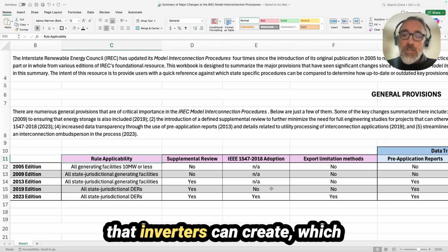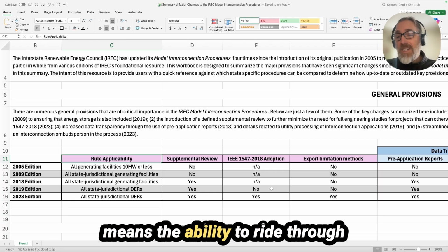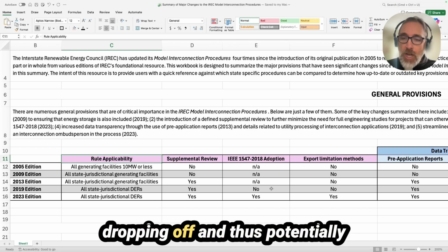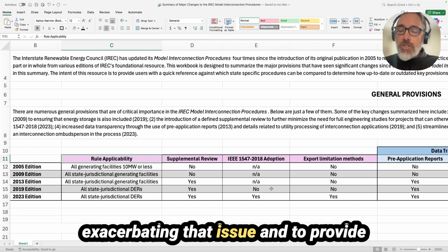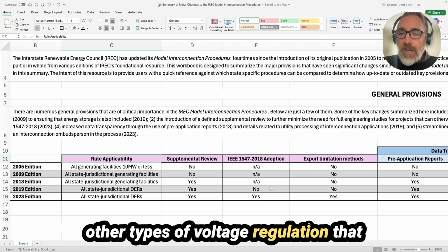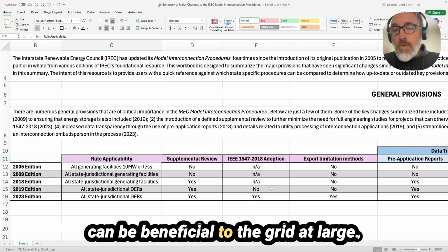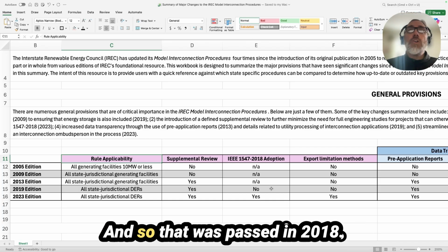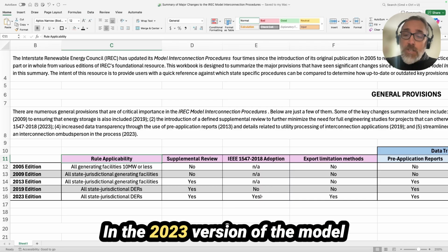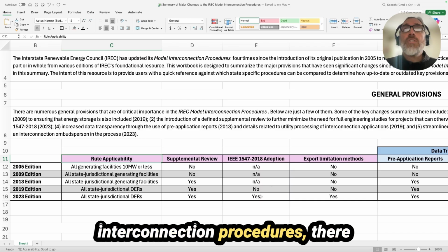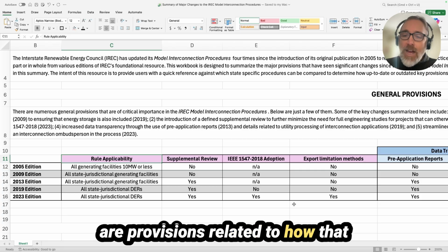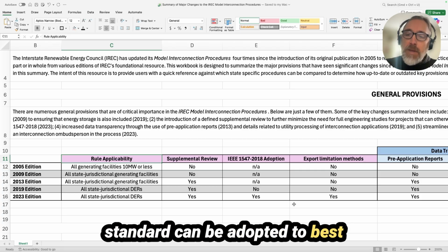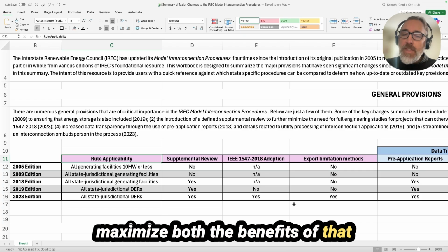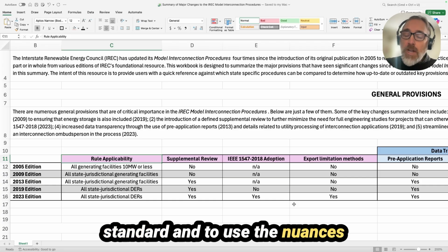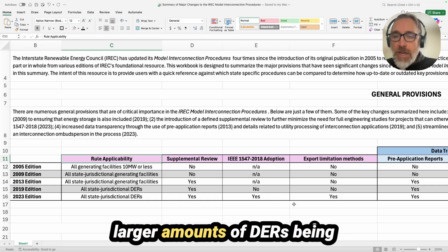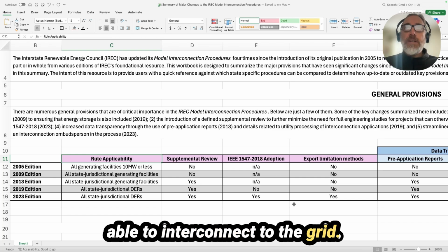that inverters can create, which means the ability to ride through higher low voltage events without dropping off and thus potentially exacerbating that issue, and to provide other types of voltage regulation that can be beneficial to the grid at large. And so that was passed in 2018. In the 2023 version of the Model Interconnection Procedures, there are provisions related to how that standard can be adopted to best maximize both the benefits of that standard and to use the nuances of that standard to facilitate larger amounts of DERs being able to interconnect to the grid.